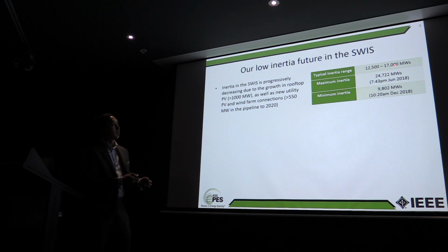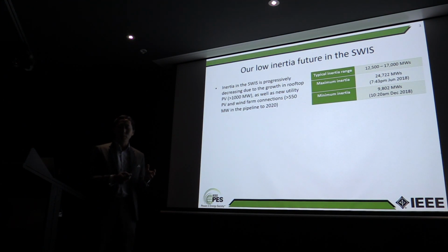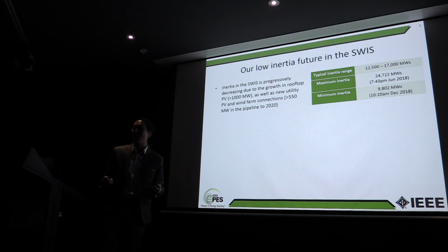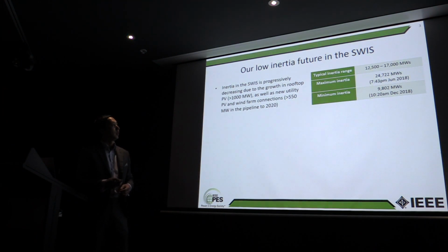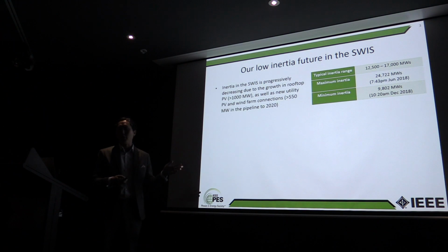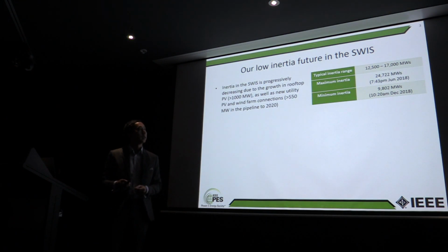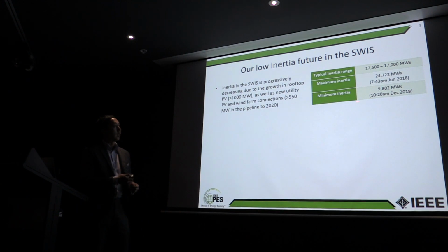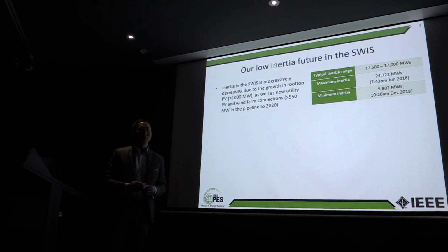seconds. Now, megawatt seconds is how we measure inertia, and if you are a keen observer, then megawatt seconds is actually joules or megajoules, which is energy. So the concept again of inertia as energy, we'll keep coming back to that. The maximum inertia in the system, about 24,722 megawatt seconds, occurred last year. Well, to be fair, it's probably higher than that because we've only been measuring inertia for the last couple of years. But the interesting point is that the minimum inertia, 9,802 megawatt seconds, occurred during the day. So 10:20 a.m. on a December day.